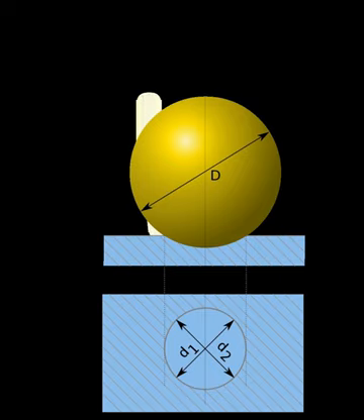For softer materials, a smaller force is used. For harder materials, a tungsten carbide ball is substituted for the steel ball.